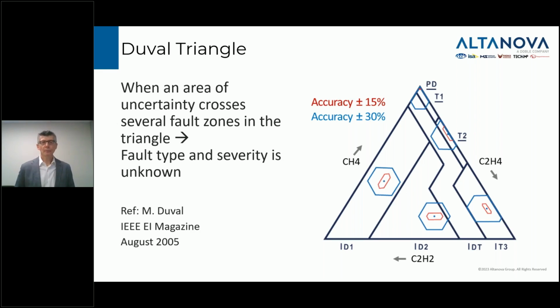What Michel did in this paper was he said, well, what if I don't know my gas concentrations perfectly, but I have a limited accuracy on them? So he drew on the triangle what it looks like if your accuracy is, say, only 15%, those are the red shapes, or if it's bigger, like 30%. I think the conclusion was that basically, if your accuracy from your monitor or your lab is about 15% or better, there's a very high likelihood you're going to land in the correct fault zone to correctly understand the nature of the fault. But if the accuracy is poorer, like 20 or 30%, maybe the odds are 50-50 that you're in the right zone doing this kind of analysis.